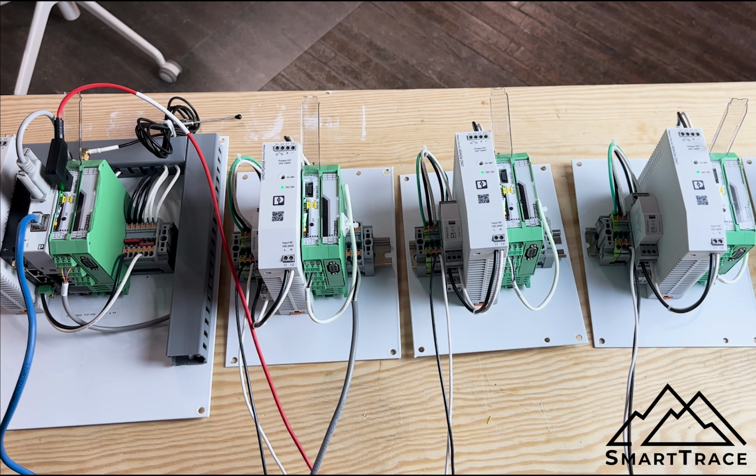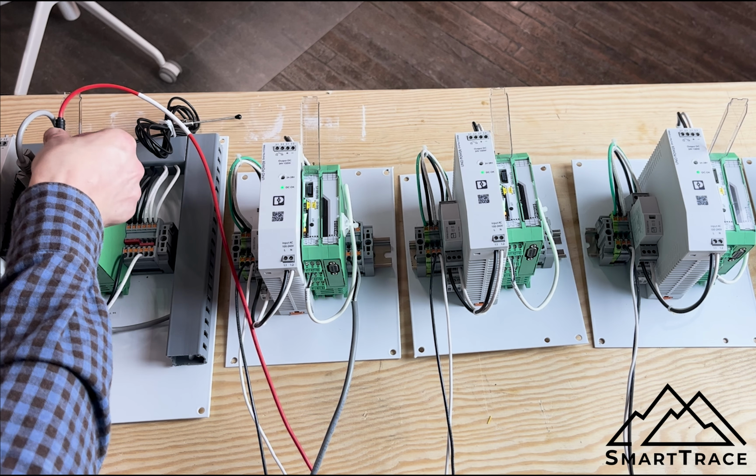So there will come a time where you will lose signal to one of the radios for whatever reason. Maybe a loss of power supply dies, some sort of issue in the antennas, maybe the actual radio itself fails. And if you have a loss of heat trace communication, you're going to need to understand what is happening with your radios. So the easiest way to do this is at your master location.